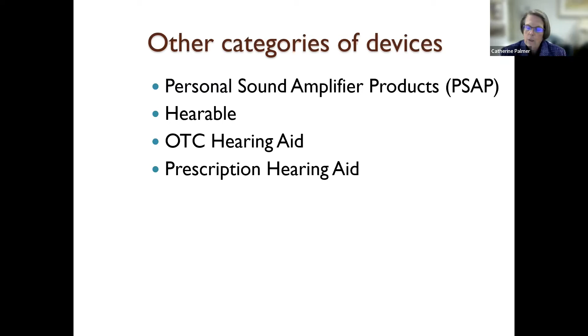So I thought I would go through just a few of the rules that came out about these devices, just in case you're interested. So the FDA first proposed that these devices could be up to 120 decibels, which is extremely loud, and would be damaging to hearing if you really exposed yourself to that, even for a short period of time. So they lowered that. So typically these won't go over 111 dB SPL. There's certain combinations where they could go up to 117 dB SPL, depending on how the circuit works. These are both levels that could injure hearing if someone really listened at this level for a long time.